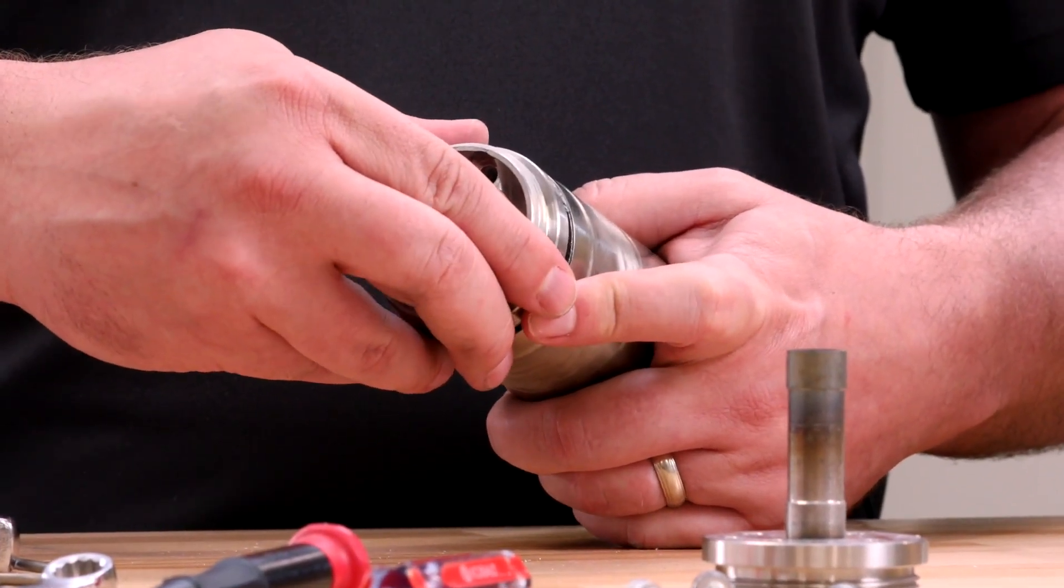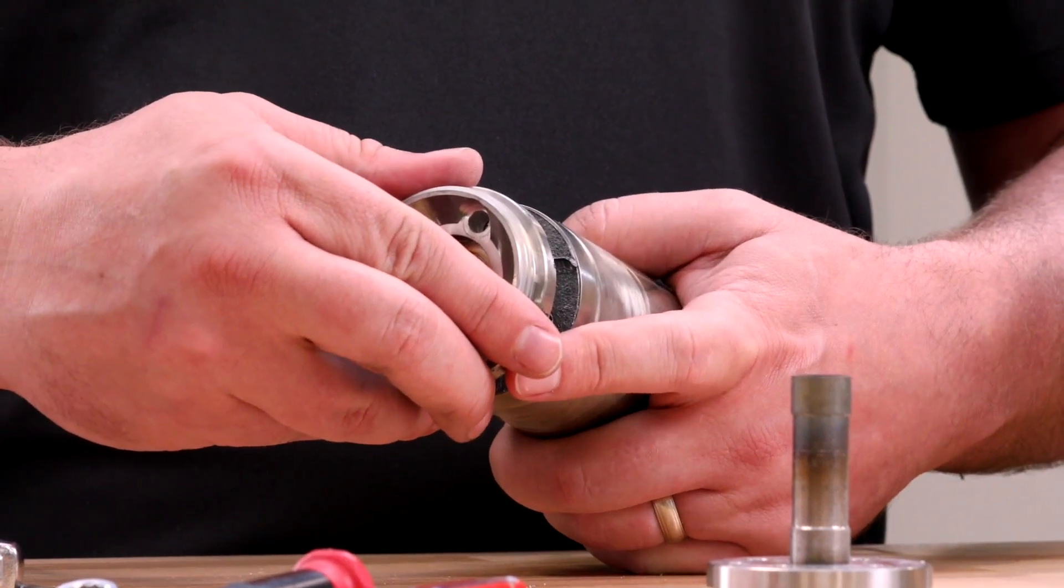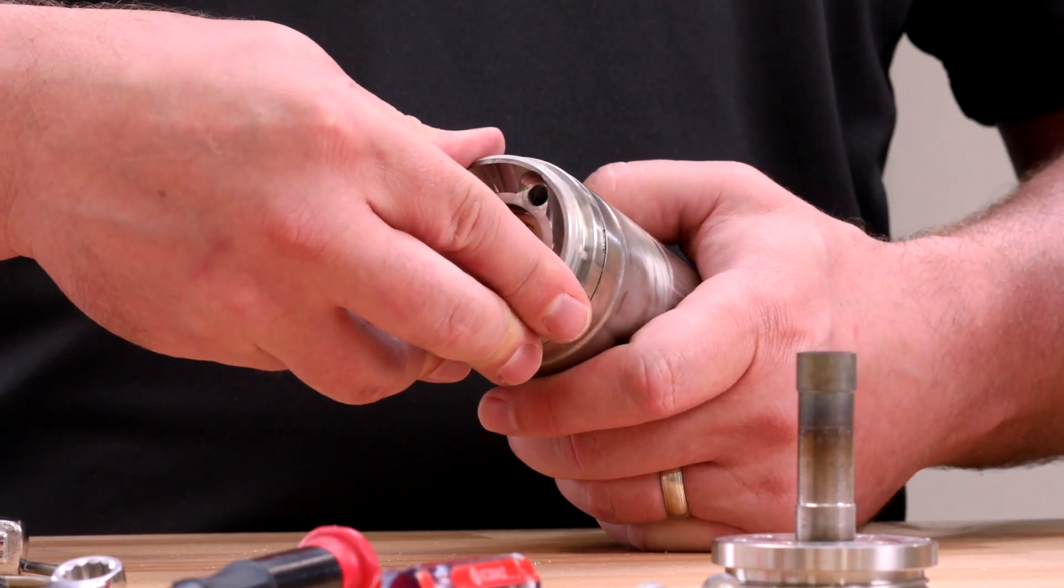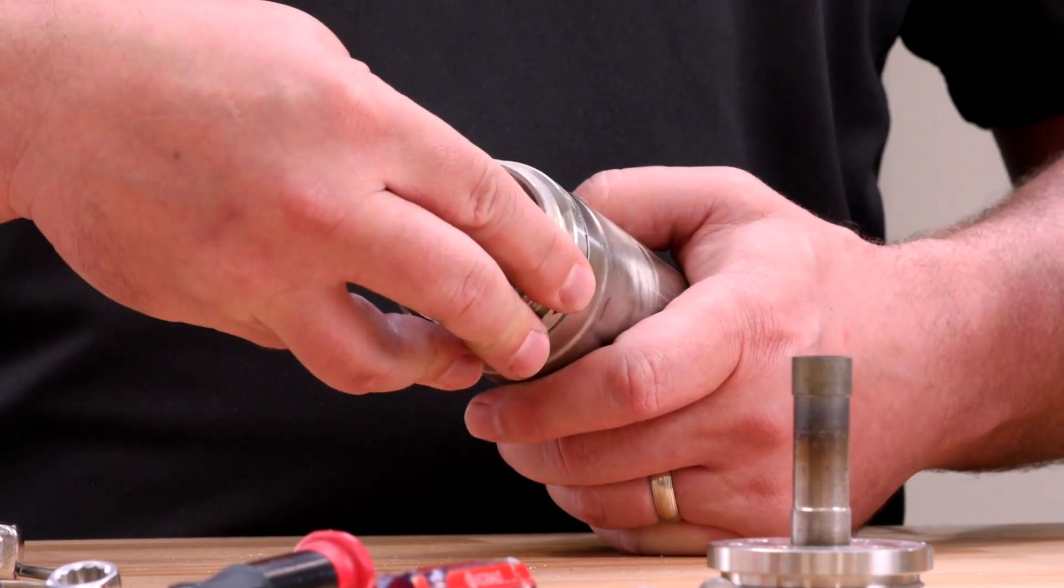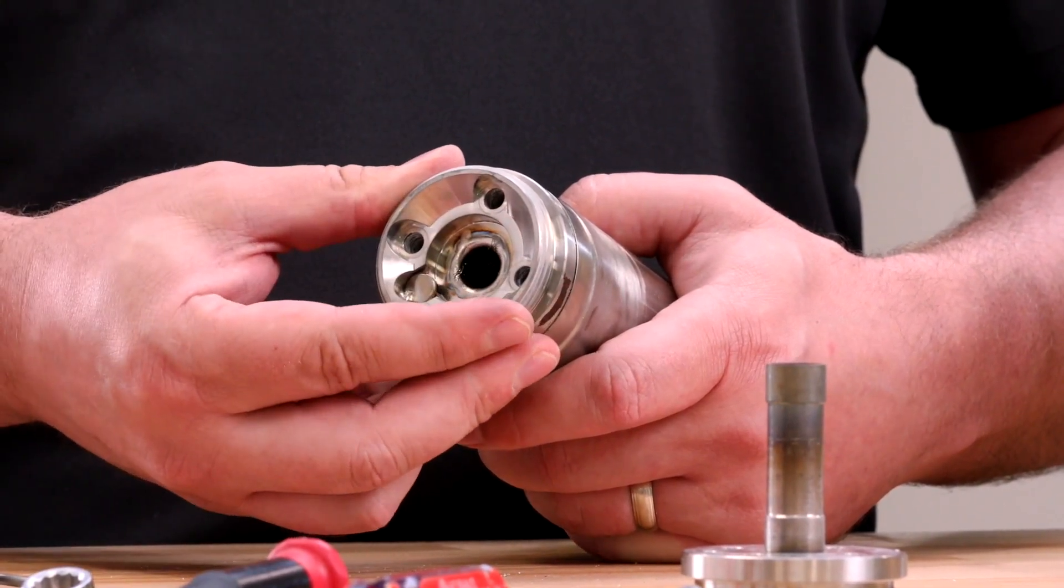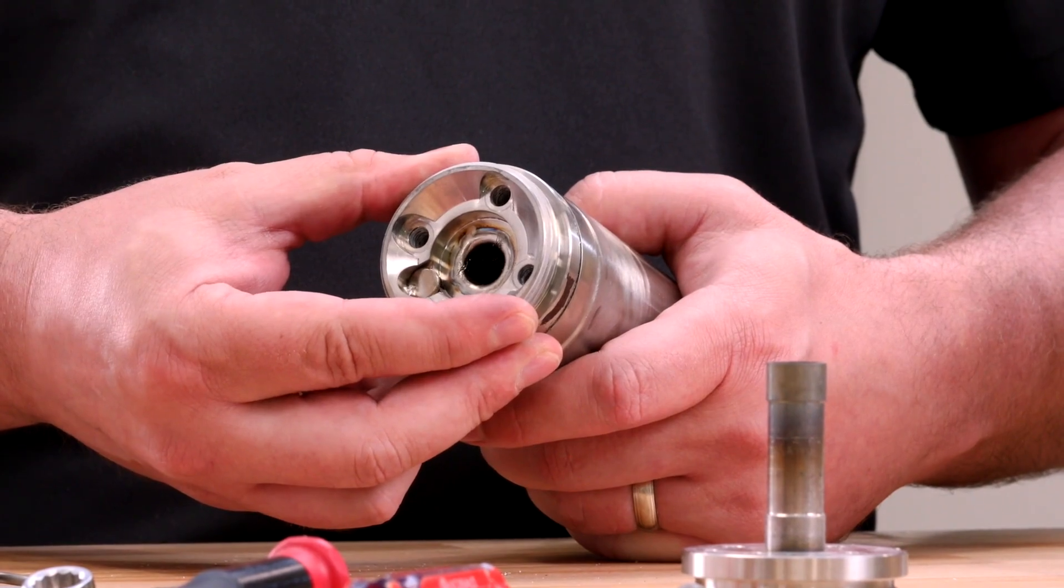If you feel resistance when removing the O2 cell, the O2 cell could be fused to the contact pad. If this occurs, push the O2 cell back into the heater tube and quickly twist the O2 cell. The cell and contact pad should separate. If the contact pad stays fused to the cell, you will need to install a new heater strut assembly.